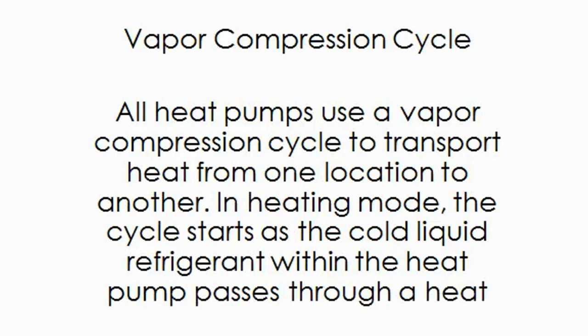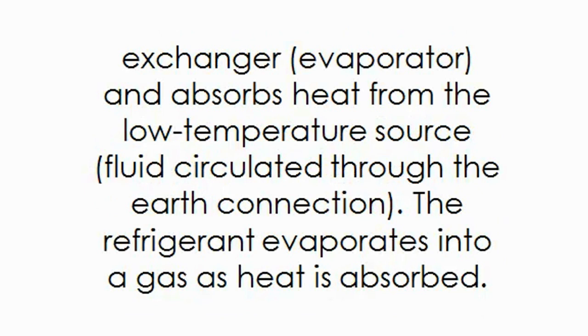Vapor compression cycle. All heat pumps use a vapor compression cycle to transport heat from one location to another. In heating mode, the cycle starts as the cold liquid refrigerant within the heat pump passes through a heat exchanger or evaporator and absorbs heat from the low-temperature source, fluid circulated through an earth connection. The refrigerant evaporates into a gas as heat is absorbed.